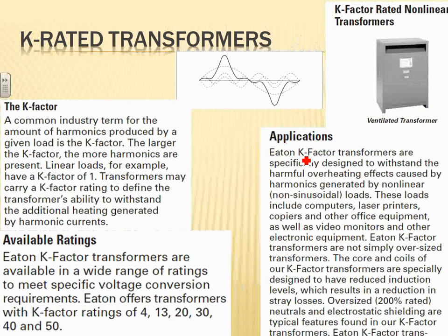Since we have a lot of harmonics right now, meaning harmonics come from any device that consumes electricity, I call them sloppy eaters. That's my term for them. The way they digest electricity, they're like my kids, they're sloppy when they eat. They don't eat it properly like a motor. They digest it differently, which means they create all these ugly waves. I don't know if you guys can see that. Believe it or not, that's screwy for your transformer and for your power system.